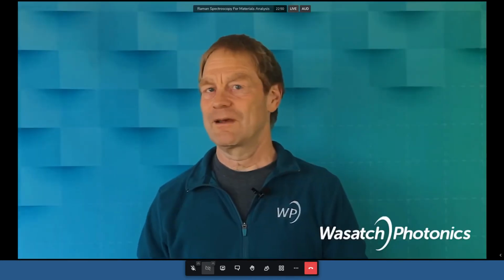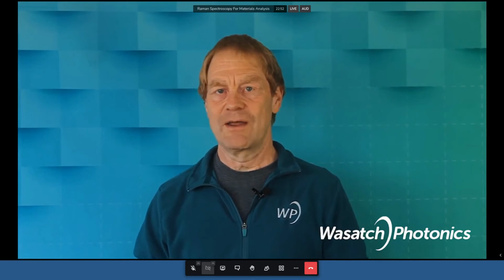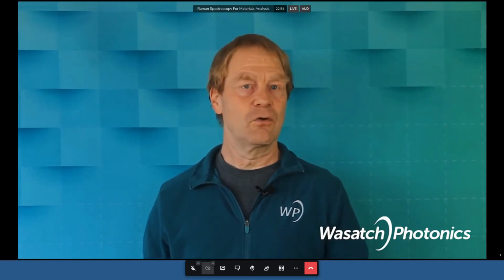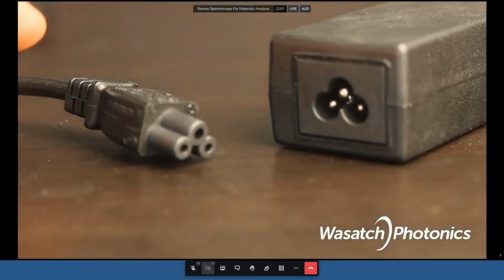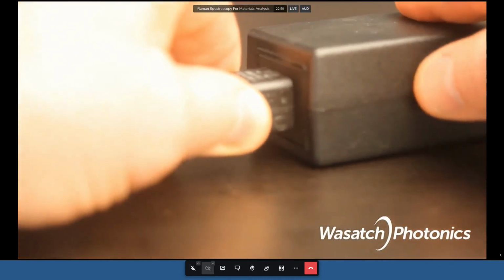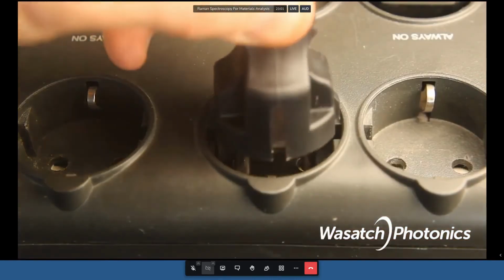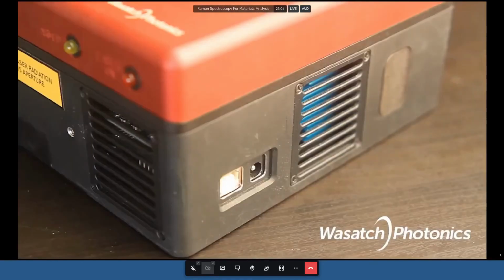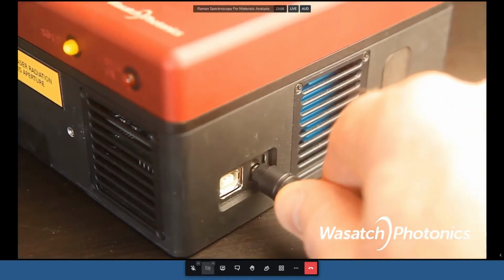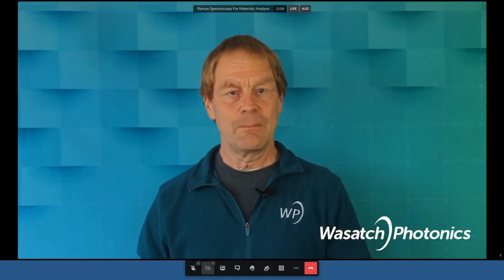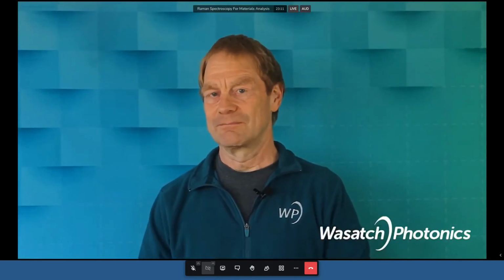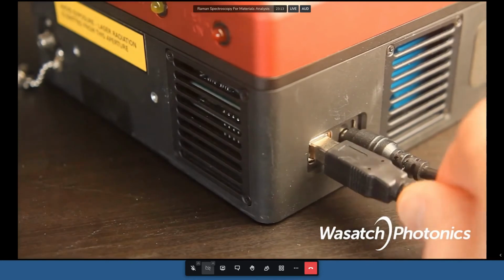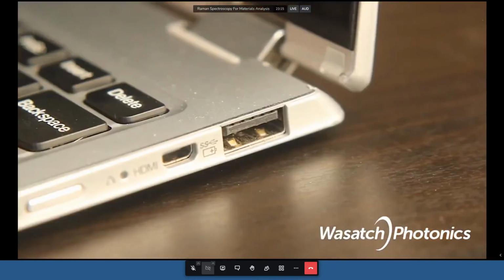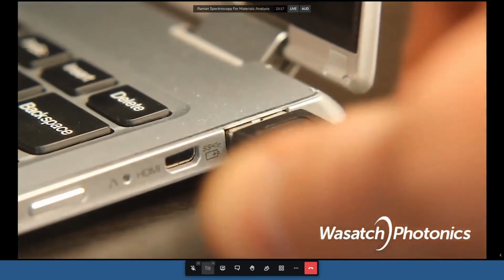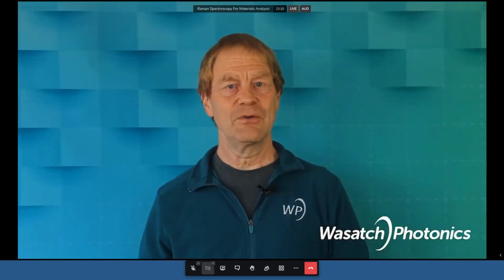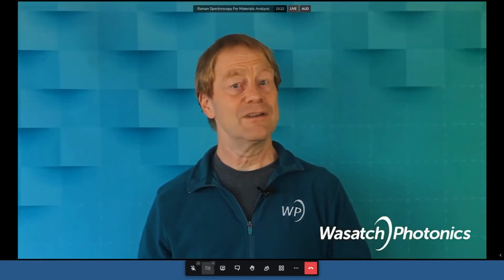Last but not least, we set up the electronics. We just need to provide power to the spectrometer and connect it to the computer with a USB cable. Plug the triangle-looking end of the power cord into the power supply and the plug end of the power cord into an outlet. Now plug the barrel connector of the power supply into the spectrometer. The spectrometer will power up. You will hear the fan starting. Next, plug the square-looking end of the USB cable into the spectrometer and the flat end of the USB cable into your computer. You should hear a friendly chime from your computer indicating that the USB communication is working.